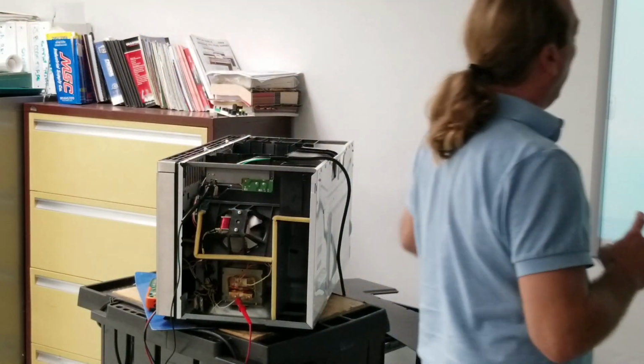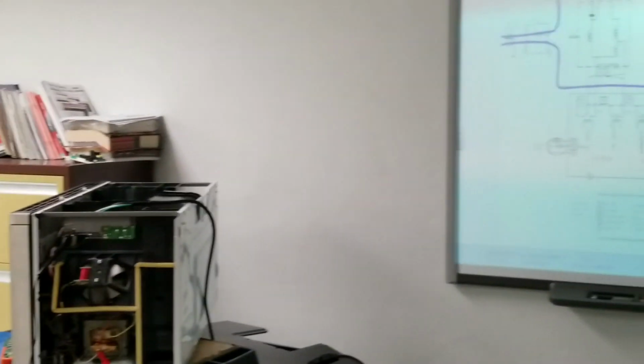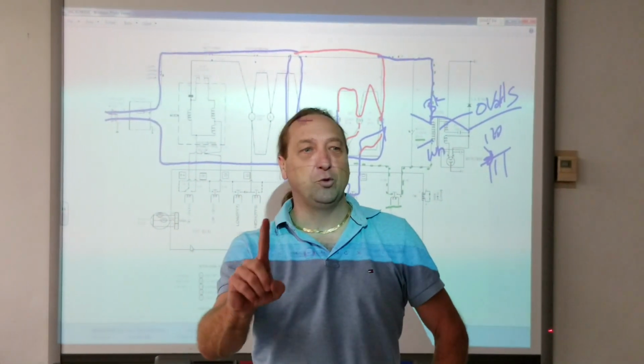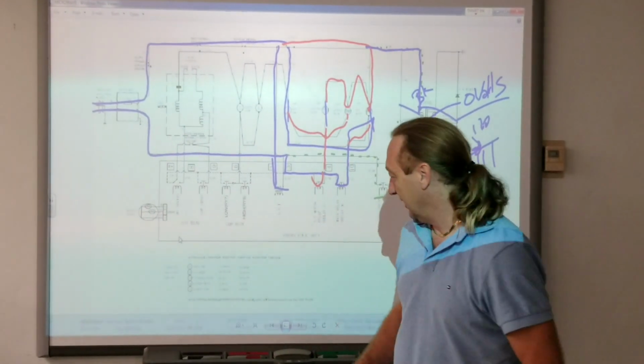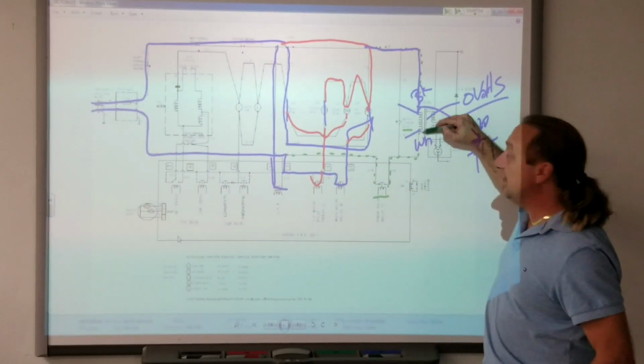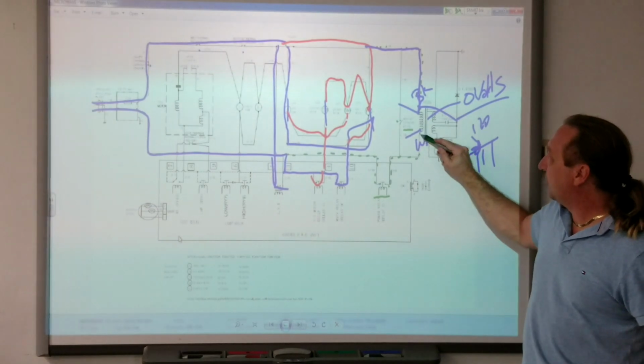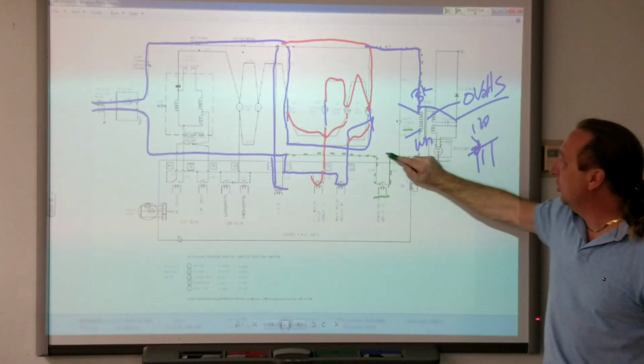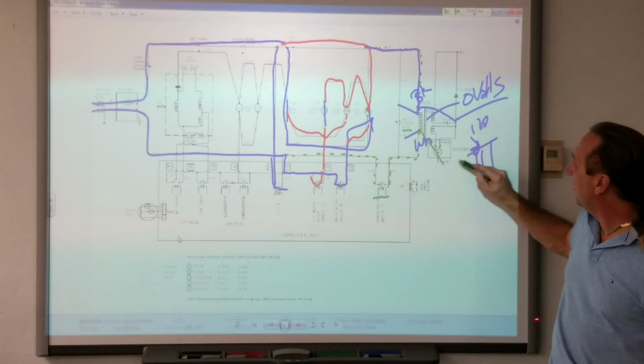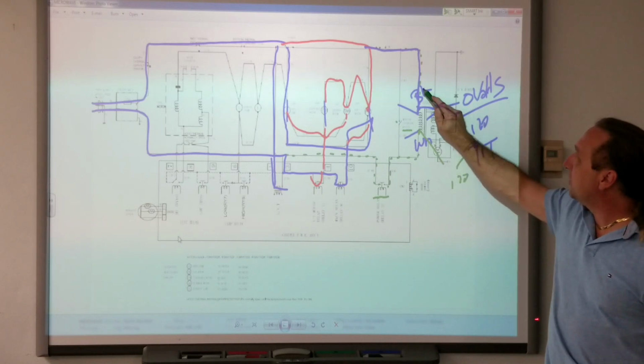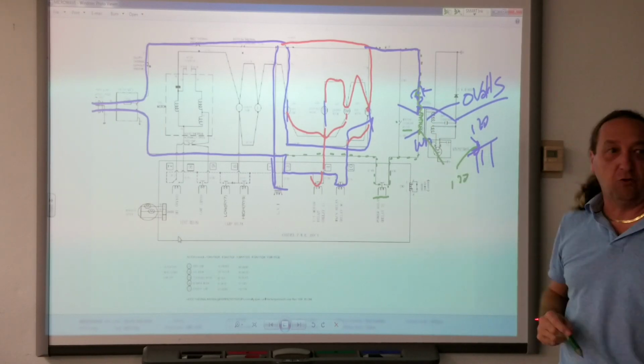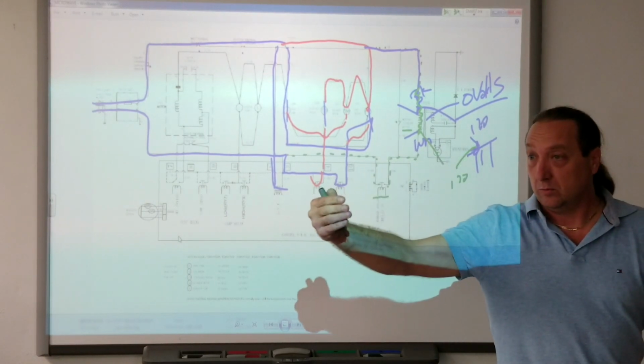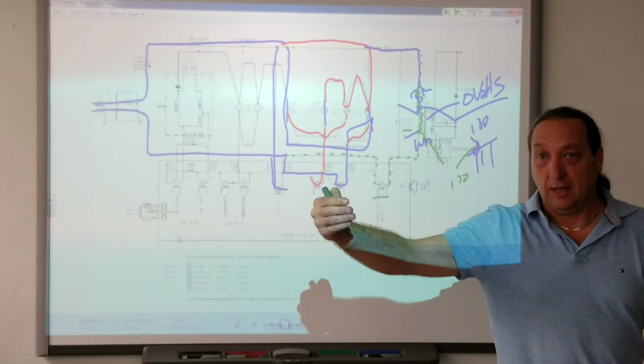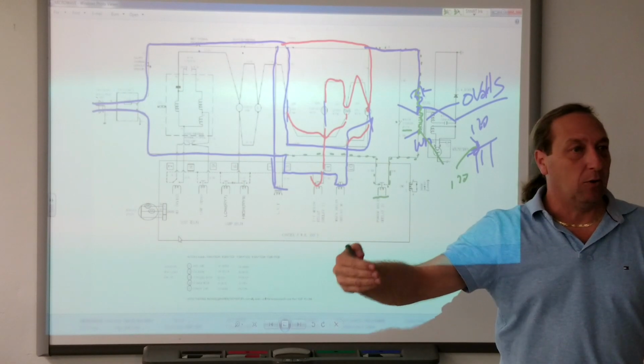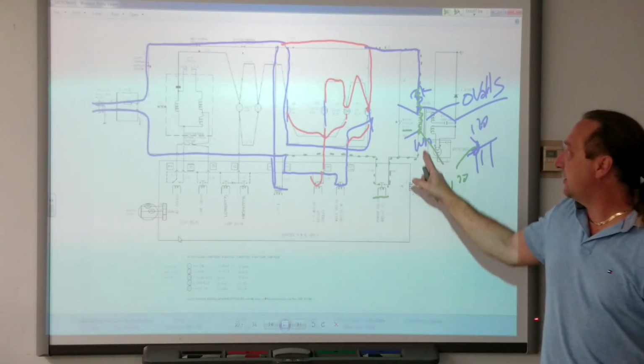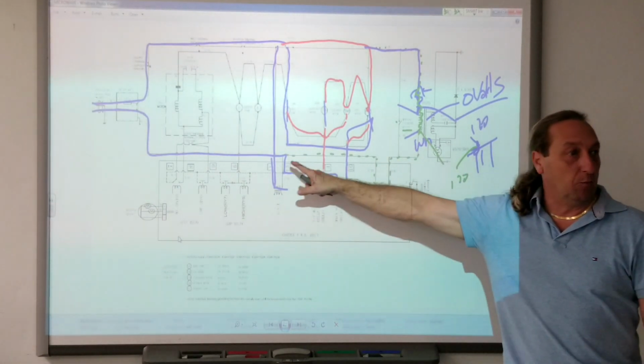Because what should white to ground give me? Zero. 0 volts. Why do I have voltage from white to ground? What's happening is that the winding in the transformer is good. Somewhere here, I'm losing my voltage. From here to ground, I have 120. So line 1 is coming through the transformer. It's feeding through. I'm still getting power on the neutral side because it's not neutral anymore. There's a break somewhere here. I see.